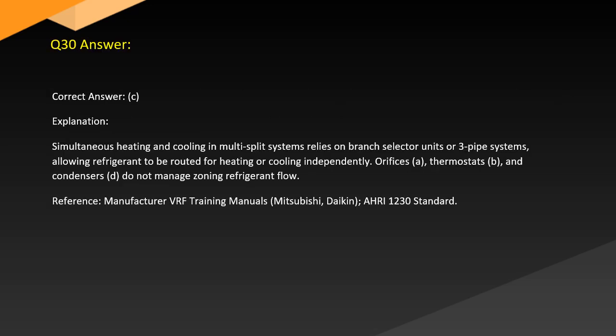Answer. Correct answer, C. Explanation. Simultaneous heating and cooling in multi-split systems relies on branch selector units or three-pipe systems, allowing refrigerant to be routed for heating or cooling independently. Orifices, A, thermostats, B, and condensers, D, do not manage zoning refrigerant flow. Reference: manufacturer VRF training manuals, Mitsubishi, Daikin, AHRI 1230 Standard.